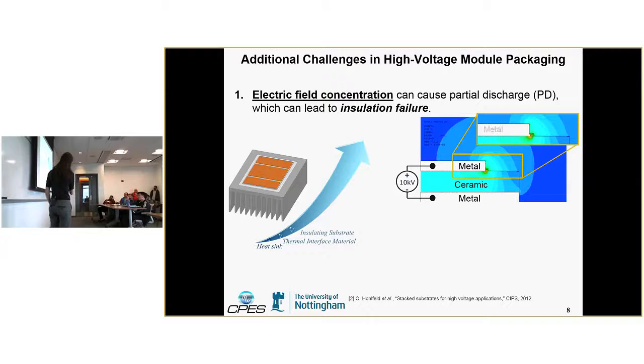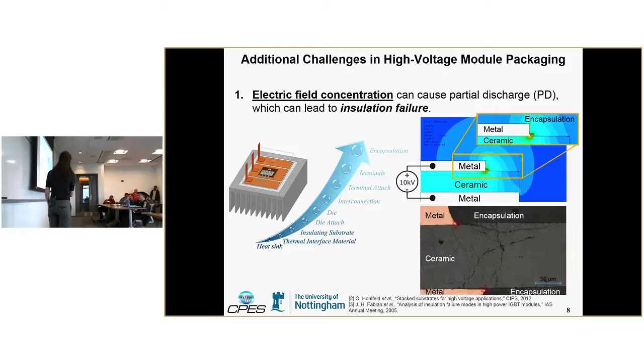But where your metal, ceramic, and encapsulation meet - the encapsulation again being for improved dielectric properties - that's where you get significant electric field concentration. That's actually called the triple point, and that's where your partial discharge will occur. This is an example of a real substrate, a metal-ceramic-metal substrate, where repetitive partial discharge was occurring at these triple points, and it actually led to cracking of the ceramic.